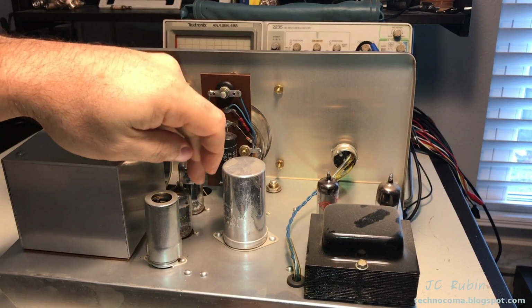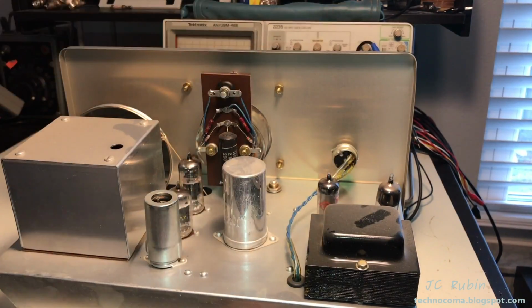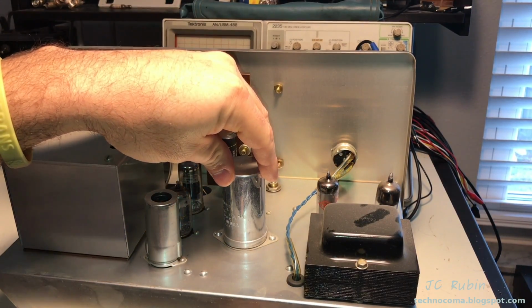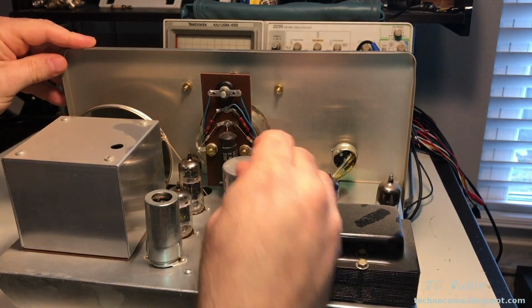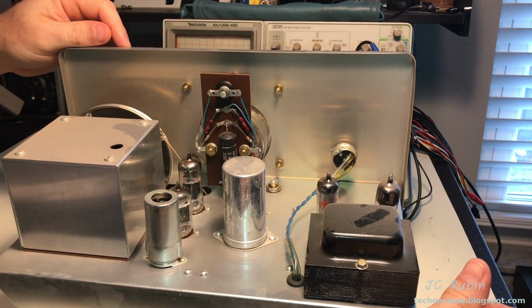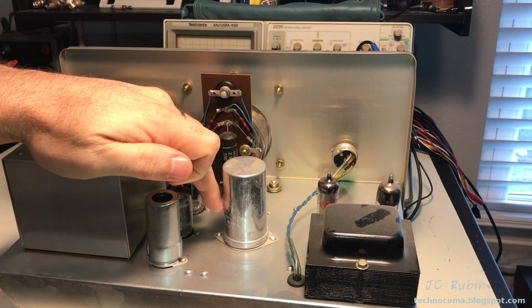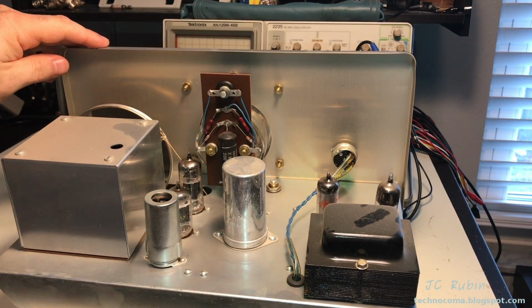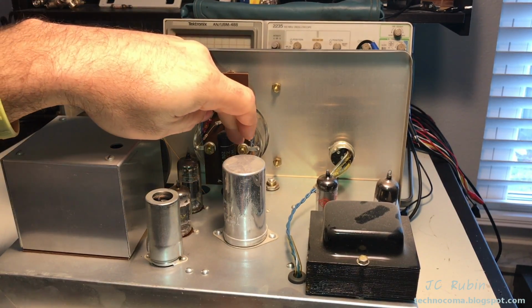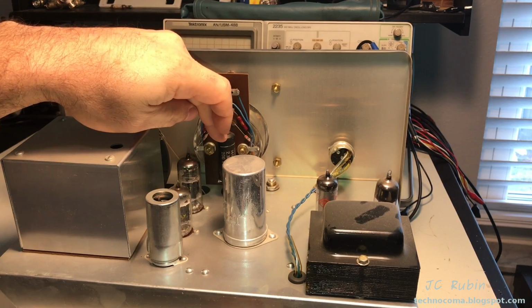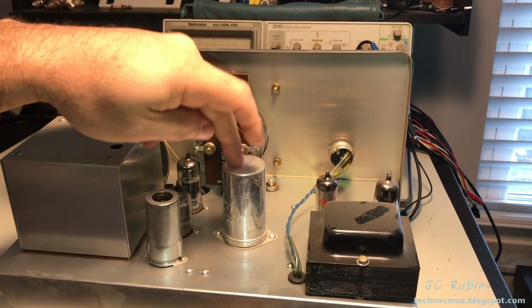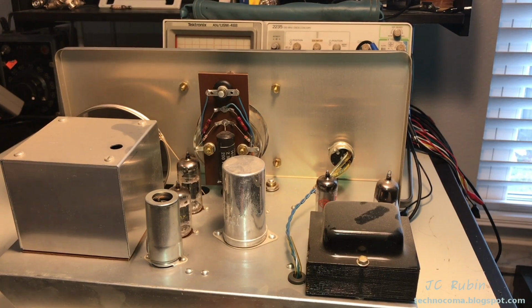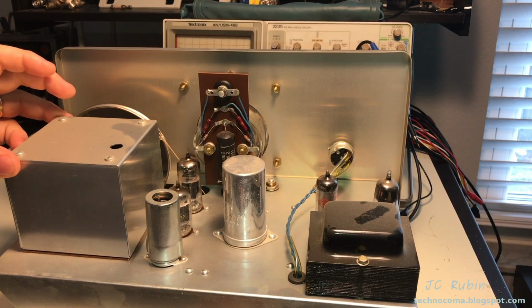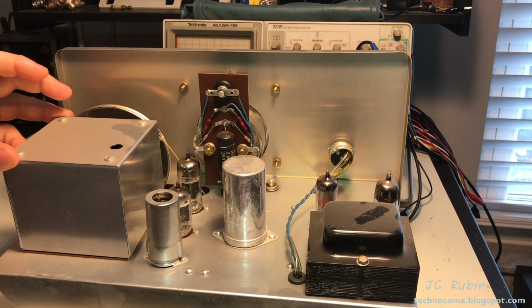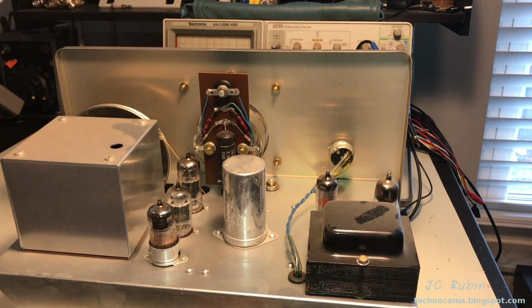We see several tubes. 1, 2, 3, 4, 5, 6 tubes. One shielded. I see a multi-can or a multi-cap right here, electrolytic capacitor. I'd have to flip the unit around to see how much. I see 300 microfarad. It may only be a 300 microfarad. I stand corrected. I see another one up here. Looks like 2 microfarad. These are ones that are definitely going to have to be checked. No problem at all. There's a container here that's separately shielded, probably due to some sensitive circuitry in there. So let's take this off and have a look.